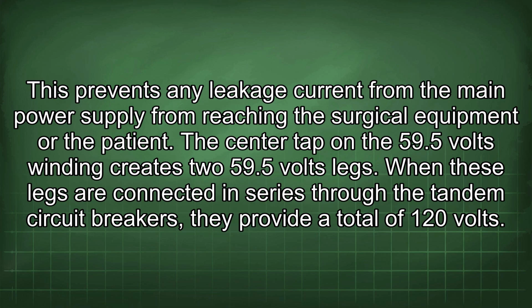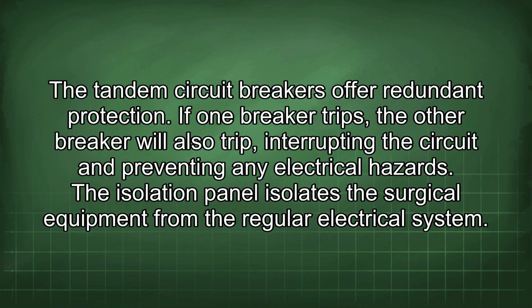The center tap on the 59.5 volts winding creates two 59.5 volts legs. When these legs are connected in series through the tandem circuit breakers, they provide a total of 120 volts. The tandem circuit breakers offer redundant protection. If one breaker trips, the other breaker will also trip, interrupting the circuit and preventing any electrical hazards.